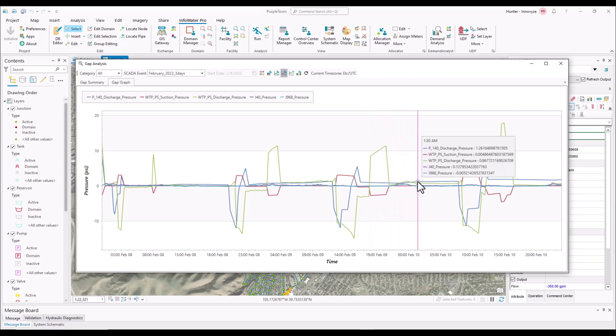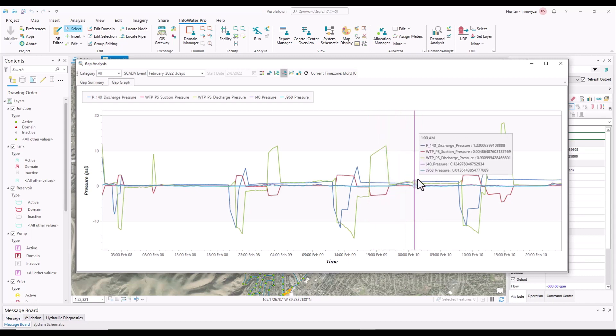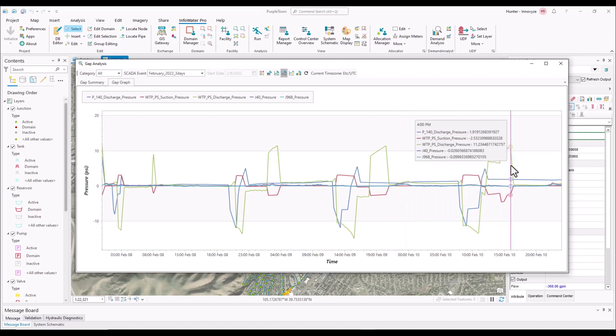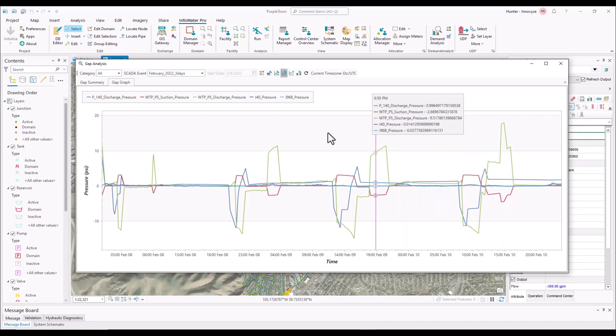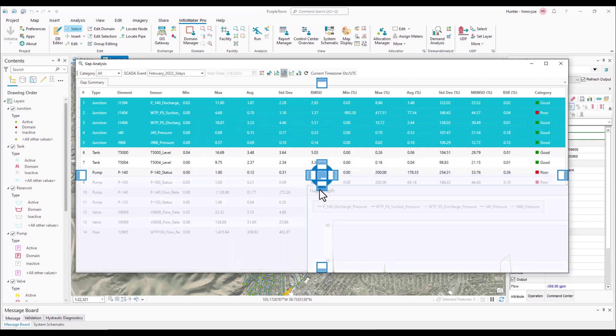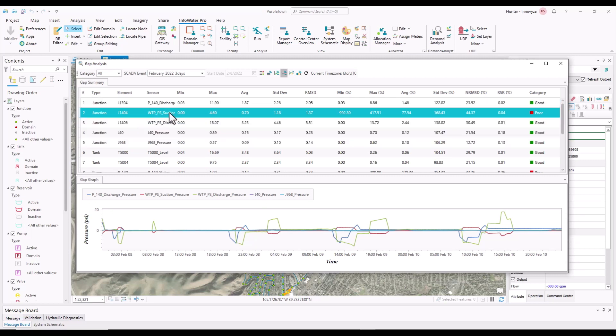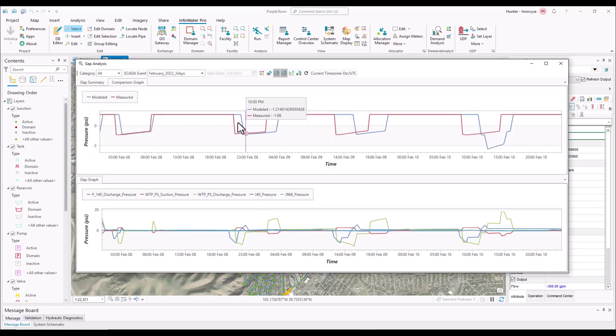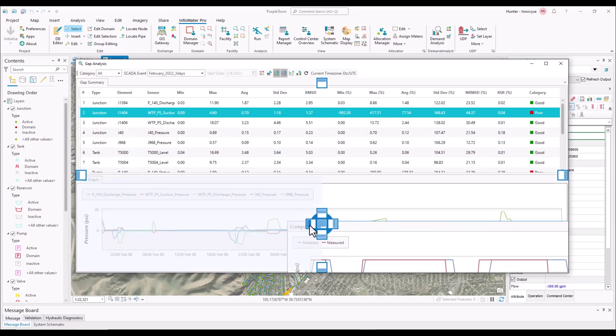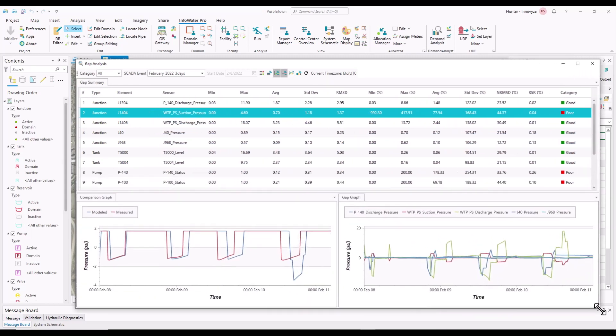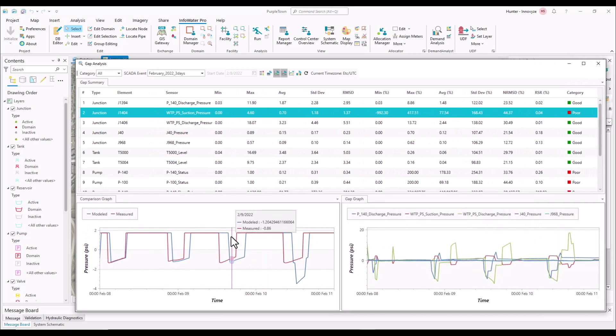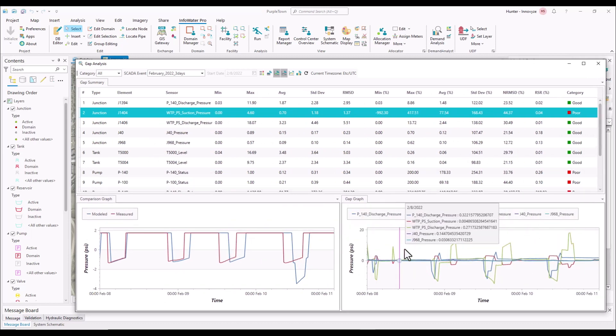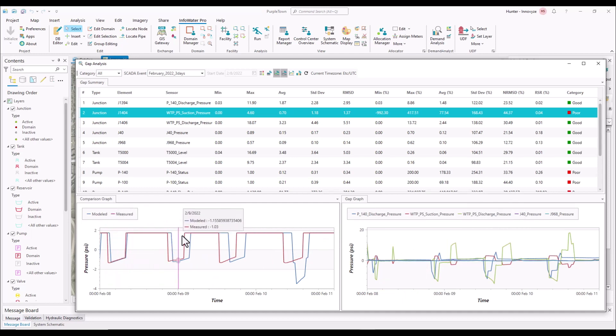So the green line is one that seems to be off a little ways. So what we can do is we can take this gap graph, we can drop it down, we can go to the J1406, which is the suction pressure. And so what we have created is a nice little workspace where we can compare multiple, as well as look at the comparison graph against that one J1406.